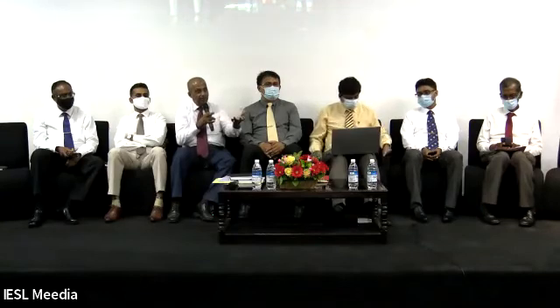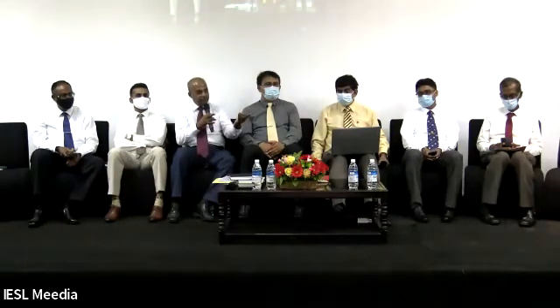So with all that, if you look at what happened in 2020 August and November 29th and December 3rd, there was an initiating event that would have been really unimportant in the whole scheme of things. But the protection system failed to operate as expected. Now, whose fault that is, I think is a discussion for another time. But the fact remains that, even in the 2020 August failure, there was a 3-phase fault. If the relay had operated within the 80 millisecond interval, none of the other things would have happened. The fault would have got isolated and nothing would have happened.